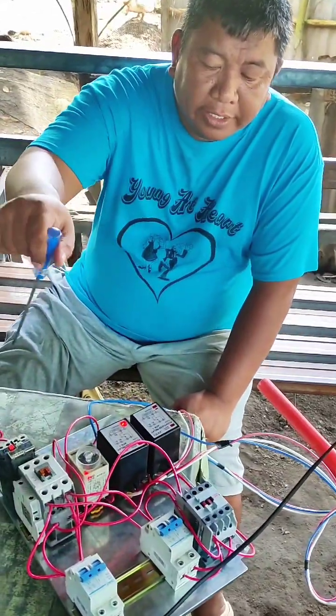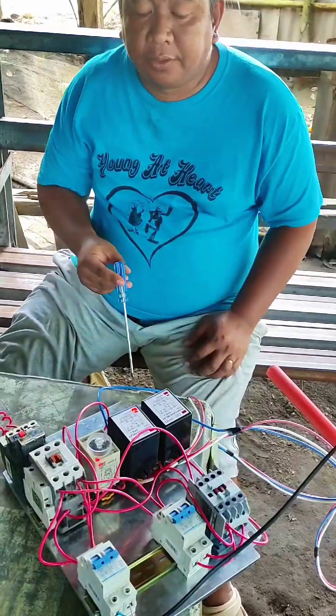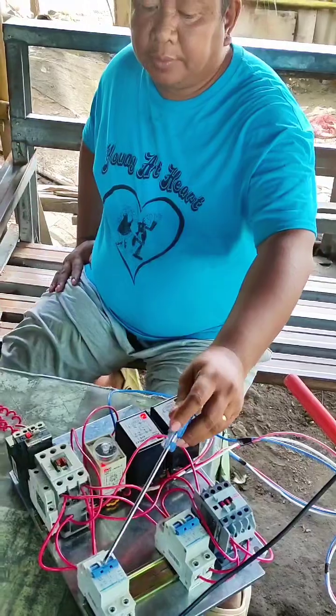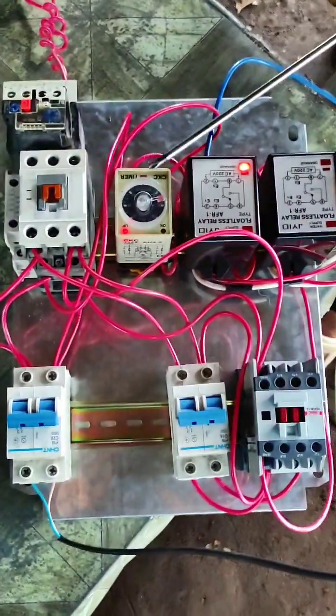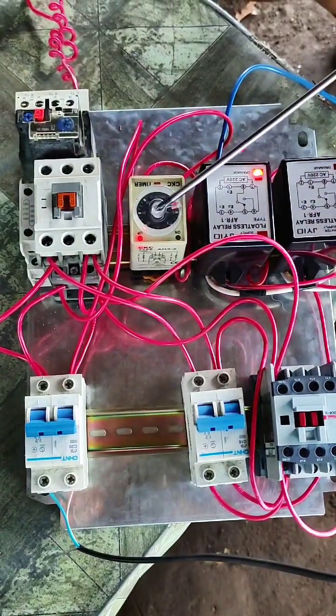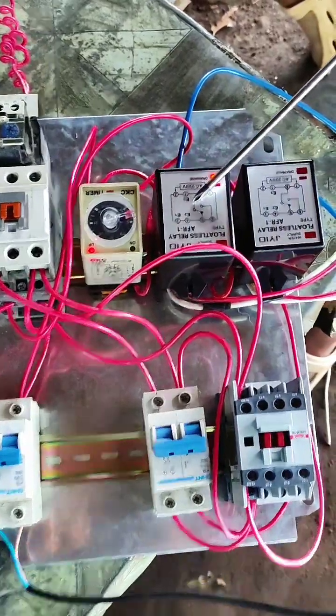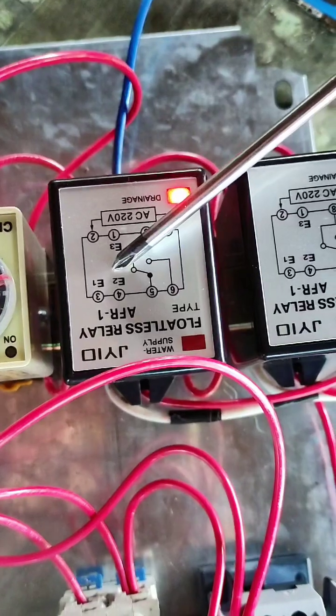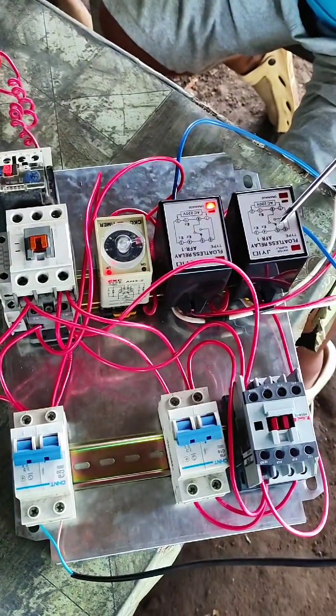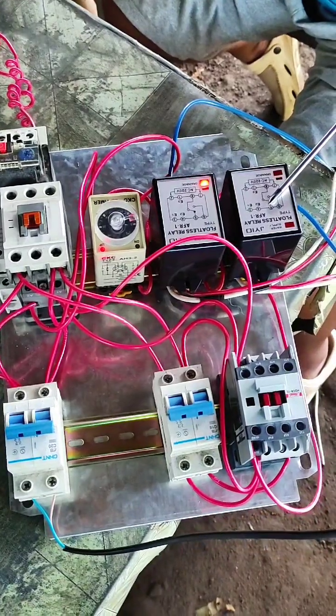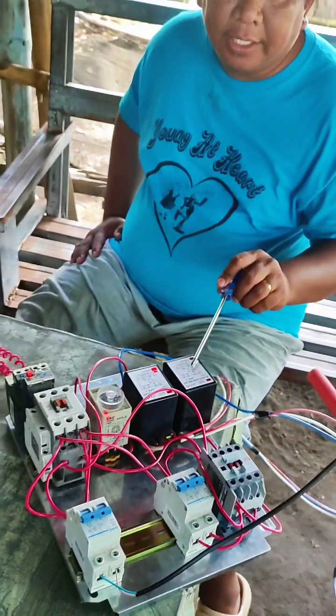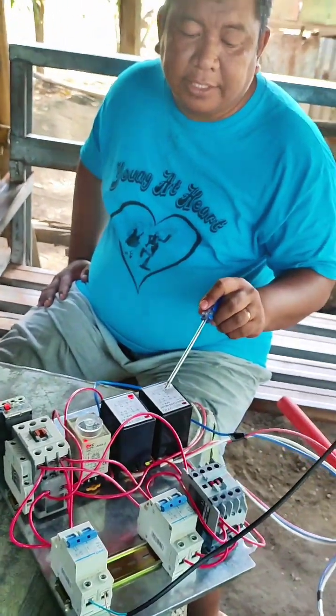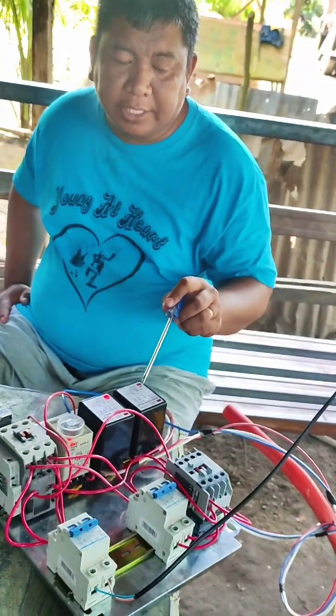We have wired here an entire system for the motor protection. There is this circuit breaker, the overload relay, and this is the timer switch, and the floatless relay, which goes for the tank. When the tank gets full, it shuts automatically, and if the tank is empty, it would automatically start the pump. And this is the floatless relay again for the motor protection. If the water well runs dry, it automatically shuts down until the water goes up to a certain level, and then it will start again.